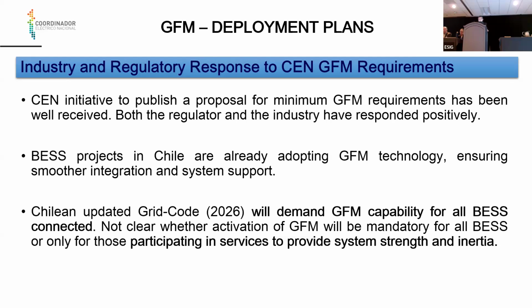The question here is that in strong grid areas with, for example, high SCR, grid forming may not be necessary, but in weak grid areas obviously it will be needed. And in this case, the question is, can we, as ISO, mandate a grid forming control mode, or must this be preceded by a study to determine the requirements and then a tendering process to participate in these services?